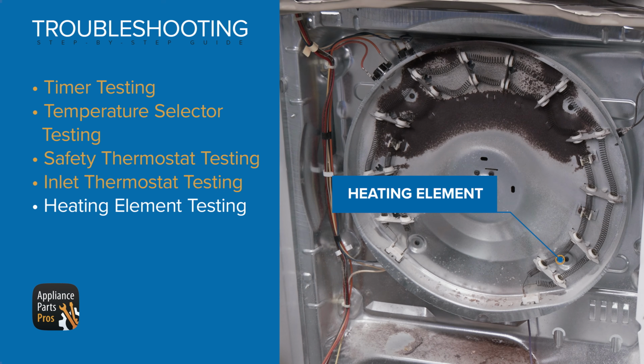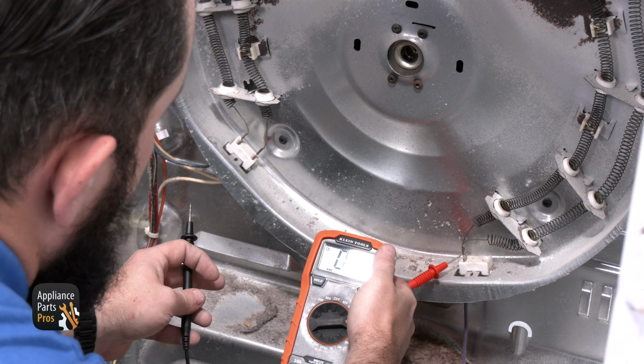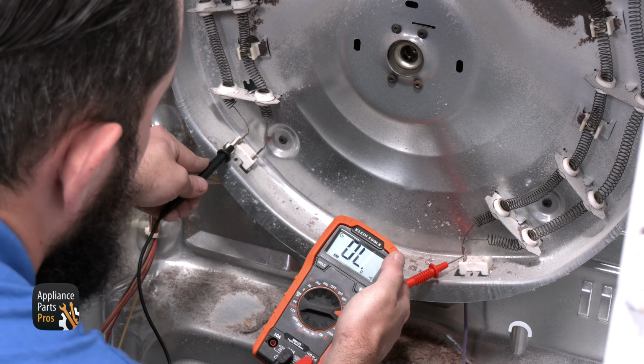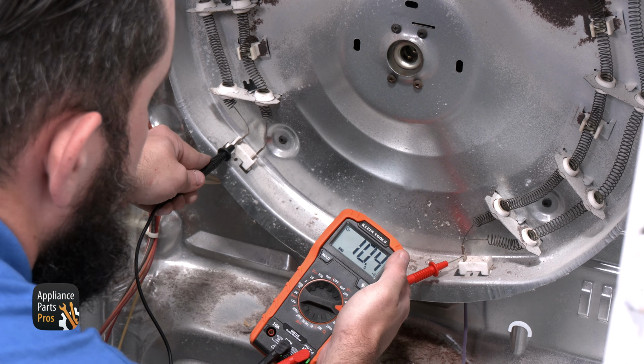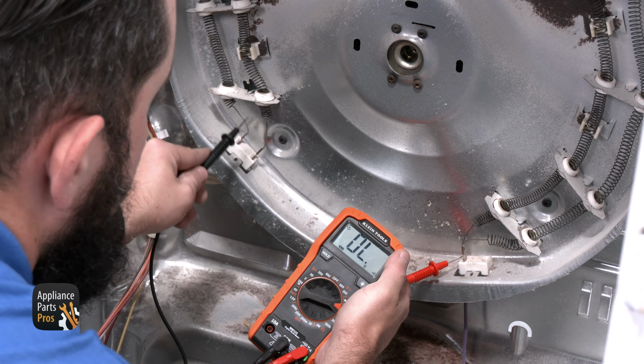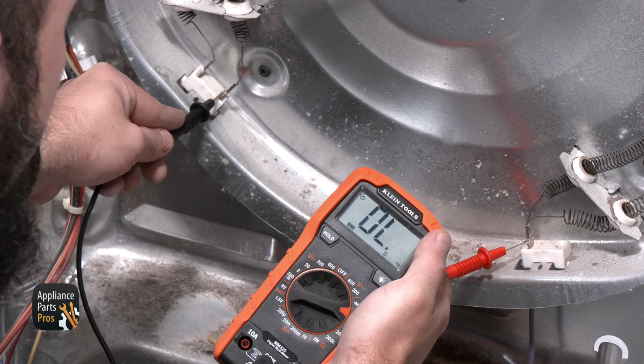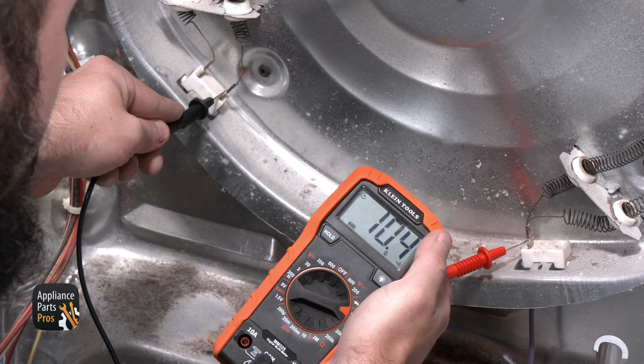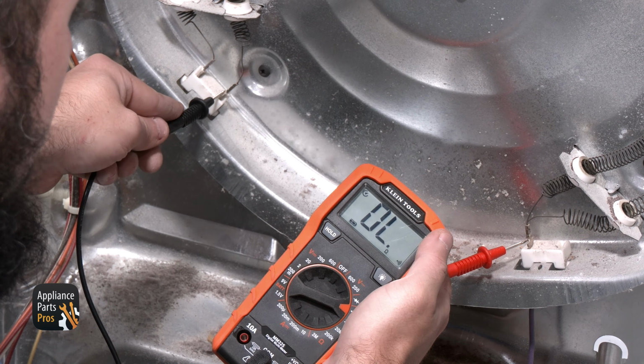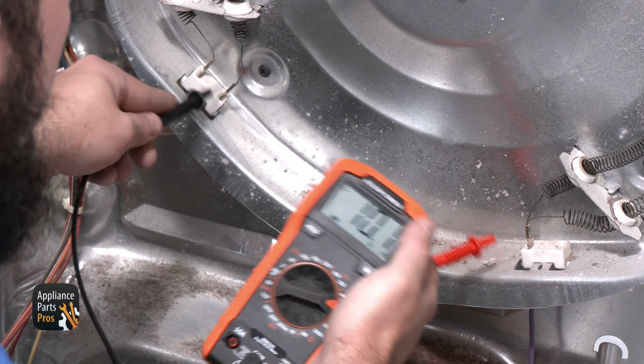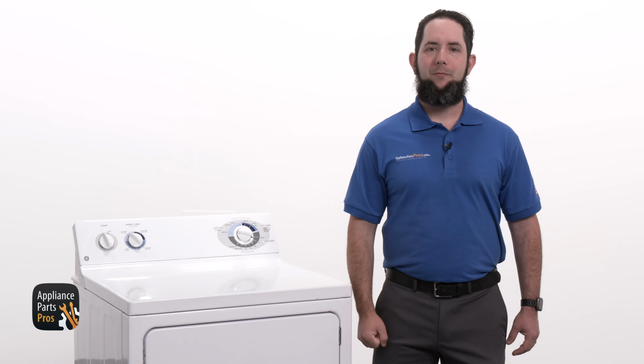Next up is the heating element, which also needs to be tested for continuity. You should see 3 terminals near the bottom of the element. We need to place one probe on the right terminal with the purple wire, then the other probe on the left terminal with the blue wire. If we get continuity here, keep the probe on the right terminal and test to the other terminal on the left with the yellow wire. If you get continuity, let's continue troubleshooting.